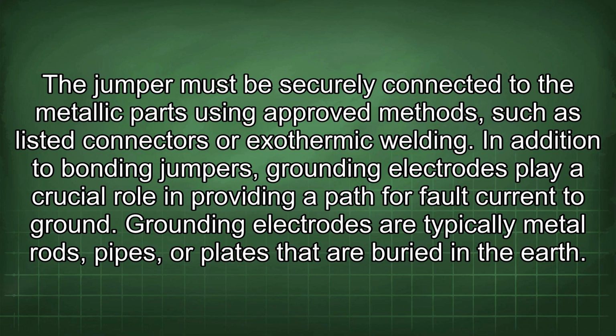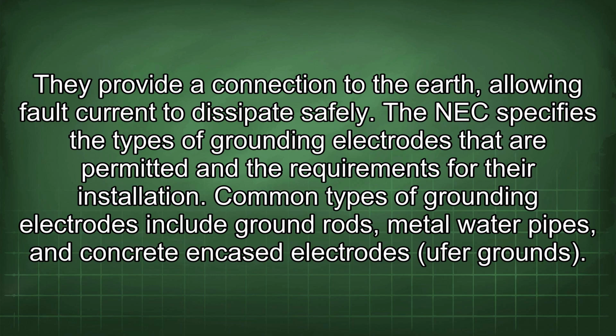In addition to bonding jumpers, grounding electrodes play a crucial role in providing a path for fault current to ground. Grounding electrodes are typically metal rods, pipes, or plates that are buried in the earth. They provide a connection to the earth, allowing fault current to dissipate safely. The NEC specifies the types of grounding electrodes that are permitted and the requirements for their installation. Common types of grounding electrodes include ground rods, metal water pipes, and concrete encased electrodes (Ufer grounds).